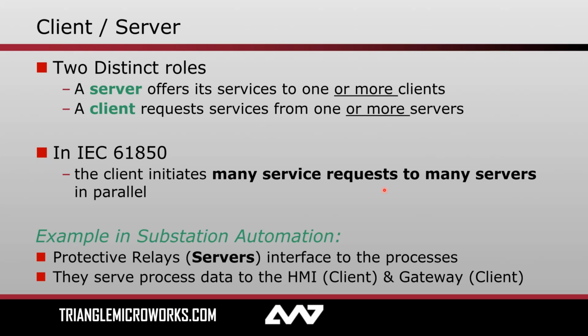Just an example of this to make it a little bit more concrete. Say we have a handful of protective relays in our substation. These would commonly be referred to as servers in 61850 terminology, or IEDs. In this case, they could send data to multiple clients, maybe a local HMI, and also a local gateway that's passing data for offsite control centers. In the same way, these clients are communicating with multiple of those servers out in the field, different protective relays or devices interfacing with conducting equipment.